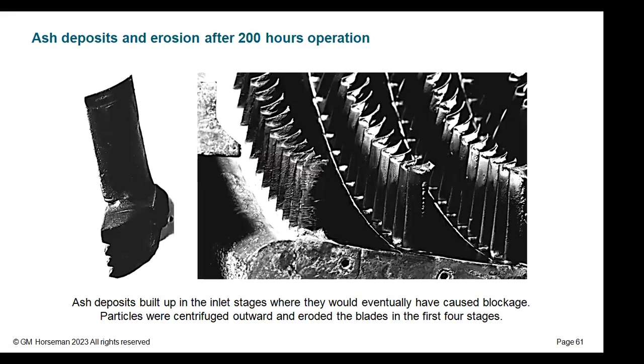That's the casing blading. So again, you can see this is after 200 hours operation. You've got deposits building up on the blades themselves. If you look closely on the blade on the left-hand side, where the blade meets the root block, you can see there's a notch being cut. That's because the slag and the ash particles were centrifuged out to the outer boundary and started cutting a knife cut into the blades. But they were eroded, blocked, and it was chemically aggressive.